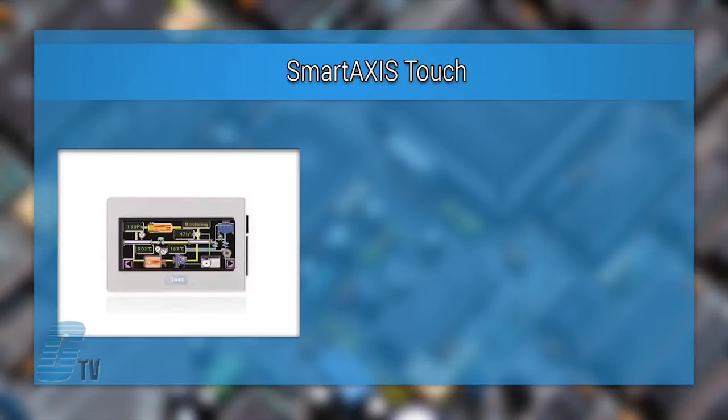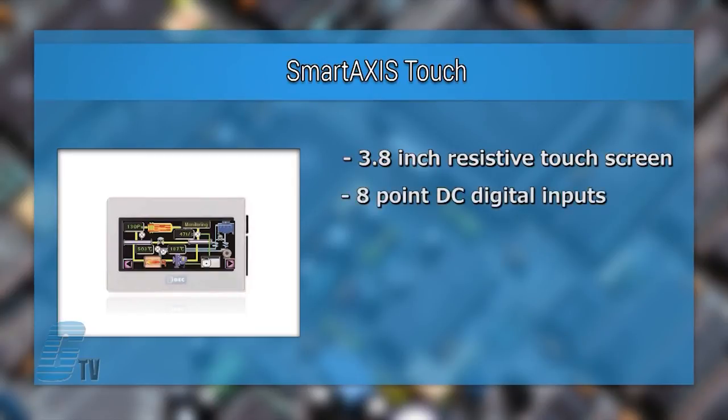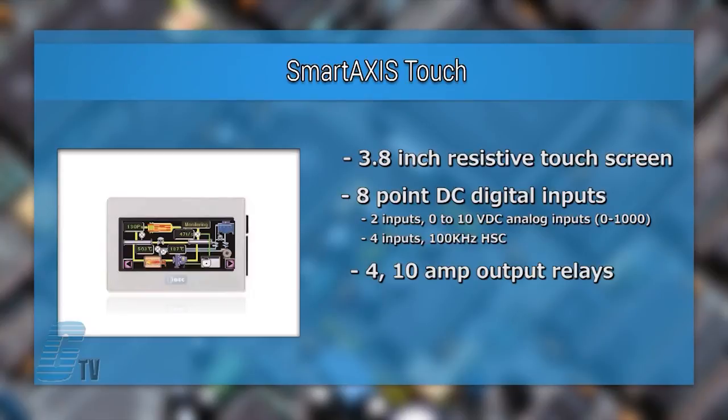The last model in this series is the SmartAXIS Touch. This PLC has a 3.8 inch resistive touch screen with 12 I/O points. There are 8 point DC digital inputs with 2 inputs configurable for 0 to 10 volt DC analog inputs and 4 inputs configurable as a 100 kHz high-speed counter. 4 relay outputs are provided and carry up to 10 amps.